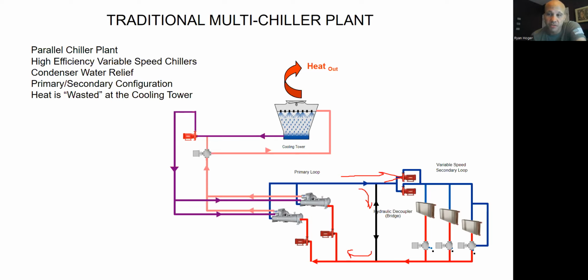We also have systems now that we call variable primary, right? So on this one, these are old school chillers, and these circulators down here probably run at a fixed speed. They just turn on and off. The chiller's on, circulator's on. These ones over here are variable speed, which means I've got a pressure sensor out here somewhere that's measuring the pressure and maintaining it with these circulators. You could also have variable primary, which means you don't have two loops on the chilled water side of the equation. What that would mean is that these circulators right here do the whole thing. They are sized to handle whatever these chillers need. Or you can think of it as these two do the whole thing.